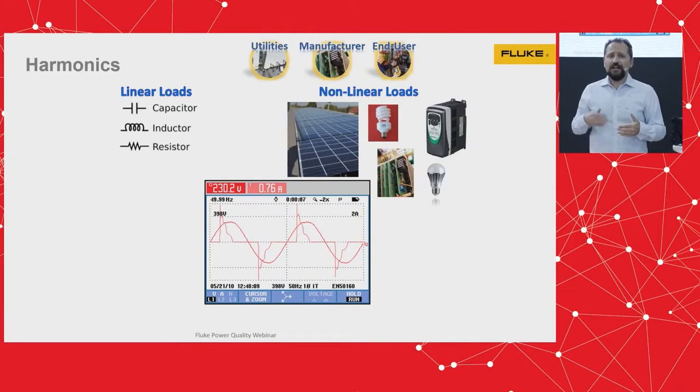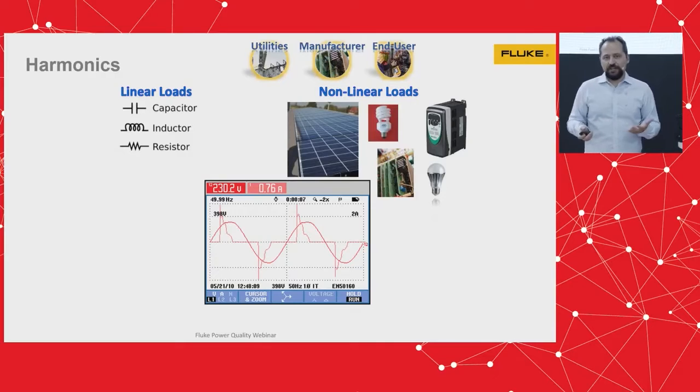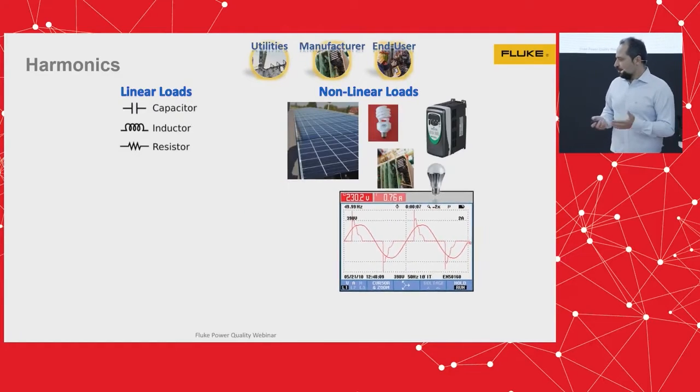They are heating up our electrical system, they are creating noise, they are creating vibration. All the issues that we were mentioning in many cases are related to harmonics. So we need to be able to sample our electrical signals really fast to be able to diagnose which harmonics are creating the issues that we are seeing and take the appropriate measures.